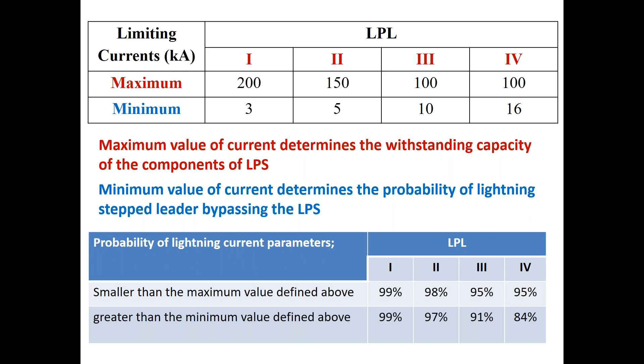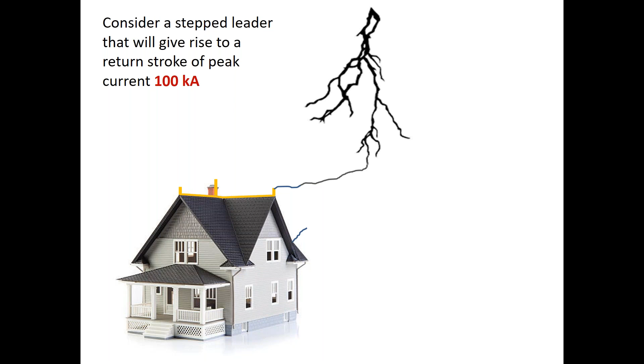Let me show you this graphically, with a small animation. Now consider a step leader that will give rise to a return stroke of 100 kiloamperes. Now you will see that, just like in the previous case, even from the same building, there can be unsuccessful leaders coming to meet the step leader. But usually if the current of the lightning is very high, that means it is bringing a very large amount of charge. In turn, a very large amount of charge brought down will give rise to a very large electric field at the tips of the lightning protection system. Therefore, a streamer will start from the lightning protection system much earlier in the case of very large current lightning that is coming towards your building.